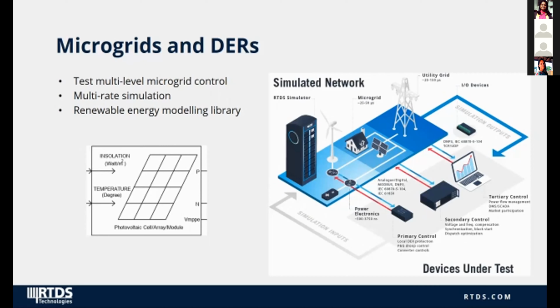In traditional distribution systems, power flow is unidirectional from generation stations to load centers. Integration of DERs introduced bidirectional power flow, which must be studied in order to determine its effects on the grid. Digital real-time simulators support multi-rate simulations. They have environments for representing portions of the network as either a fraction or a multiple of the time step of the main network.